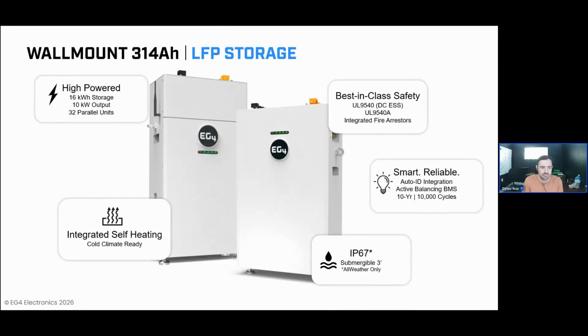And then no matter where you install it, whether it's indoors or outdoors, this unit can be counted on to deliver reliable and safe performance. It has a 10-year, 10,000 cycle warranty standard. And the stability that enables us to offer that extended warranty also shows up in regards to the safety performance with the unit. The model's been certified to UL 9540 as a DCESS. Now, what that means is a lot of the safety mechanisms that are generally required for an energy storage system, that generally will be performed by the inverter, have fully been integrated into the BMS of the battery itself. So just the battery alone now qualifies as a 9540 compliant system and can generally be paired with any 1741 compliant inverter, meaning the full suite of EG4 inverters. So this was really designed to pair up predominantly with our FlexBOSS inverter.